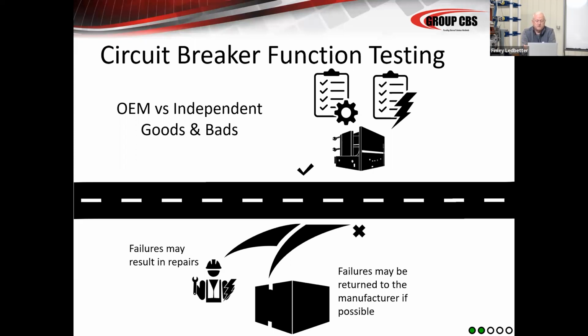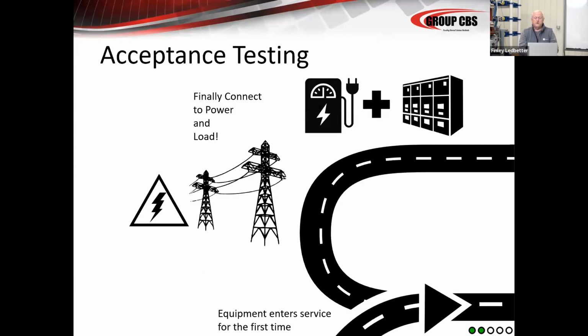There's a certain amount of electrical testing and functional testing that goes forward here. Then it comes out of acceptance testing and you're ready to energize it. So you've done your electrical testing, you do your final test, you've phased everything, you've tested everything, hopefully with full voltage, and you connect it to the load and you start to conduct power, and it starts to do work, actually, is what that's called.